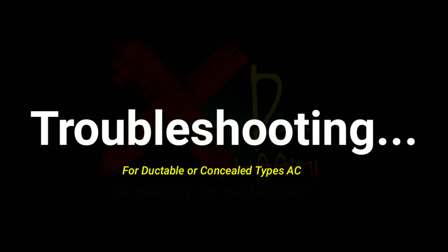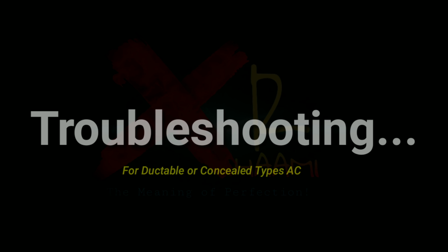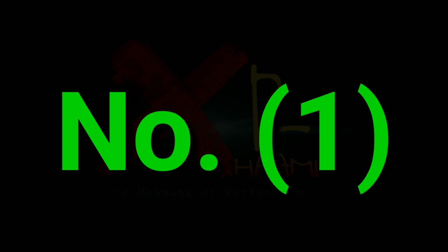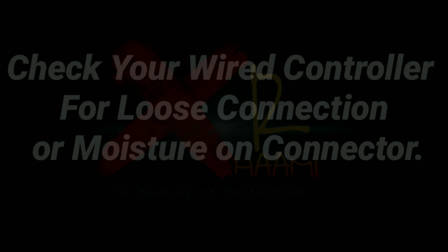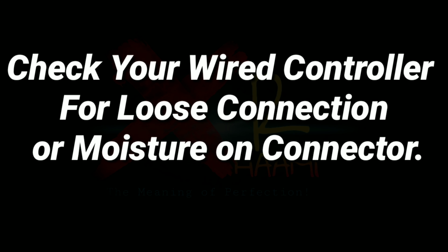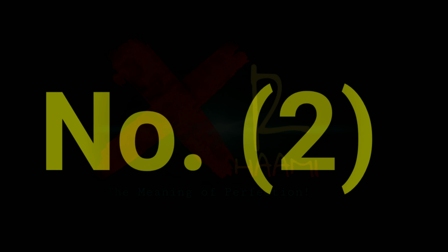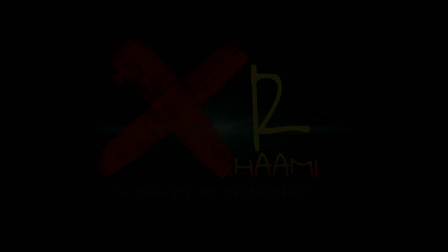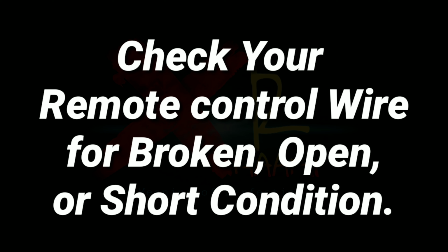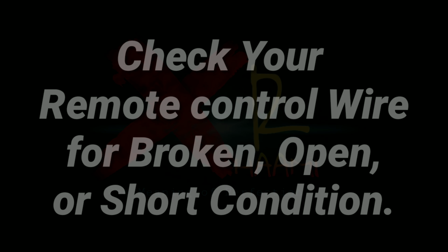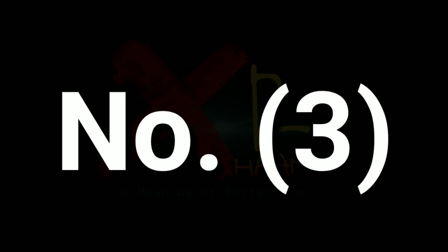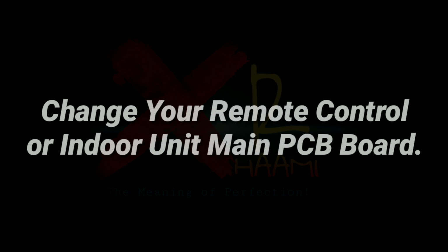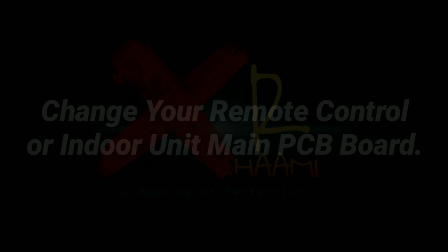Let's see troubleshooting. That types of unit who support wired control remote. Number 1 is check your wired controller for loose connection or moisture on connectors. Number 2, check your remote control wire for broken, open or in short condition. Number 3, change your remote control or indoor unit main PCB board.